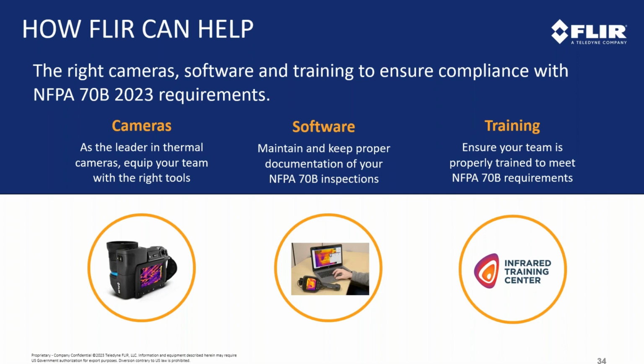We have additional functionality just released around route-based inspections. So being able to load a list of all your electrical assets that need to be inspected right on the camera, to be able to go out and systematically perform those inspections, and then use report templates. We now provide a free report template for our Thermal Studio Pro customers. It's an NFPA compliance template, performs all the calculations for you, and determines that your assets are being inspected properly. And like I said, that software itself maintains those records, to be able to document that those things have happened.